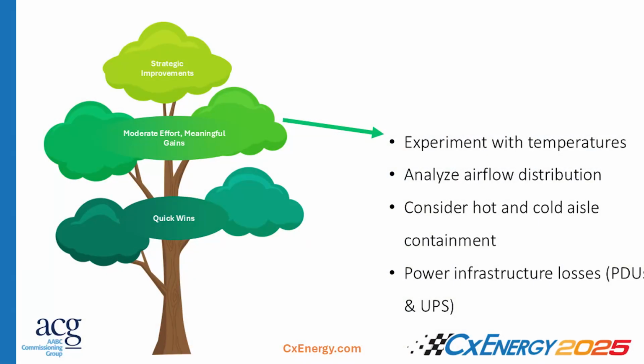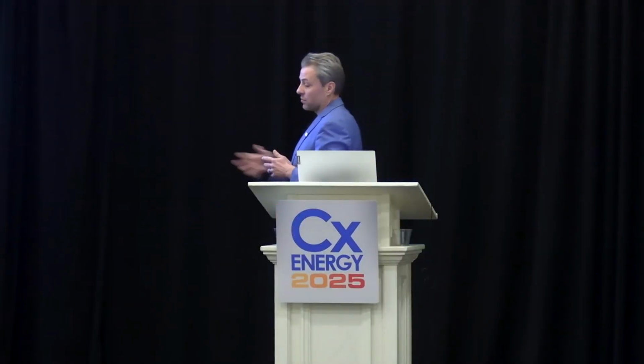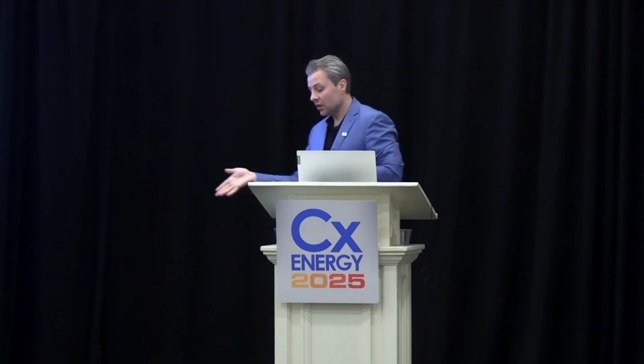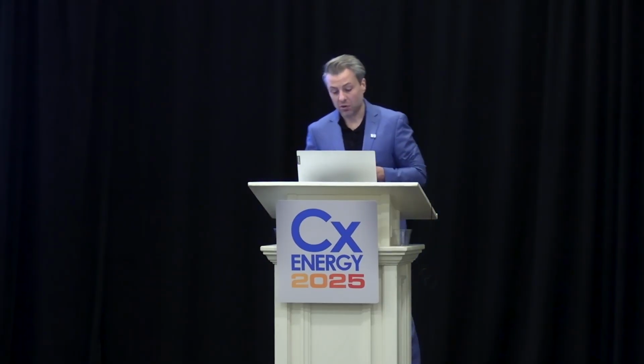So a medium hanging fruit, experiment with temperatures within limits, not like what I said, but the servers are becoming more tolerant, the ones that are still air cooled, of higher temperatures. So maybe you can go from 70 degrees up to 80 degrees and nothing happens. Talk it over with the data center manager before you really put this in your report. Analyze airflow distribution. Like I was saying, don't just pick up tiles and move them. Let's analyze where we need the air and then move the tiles accordingly.